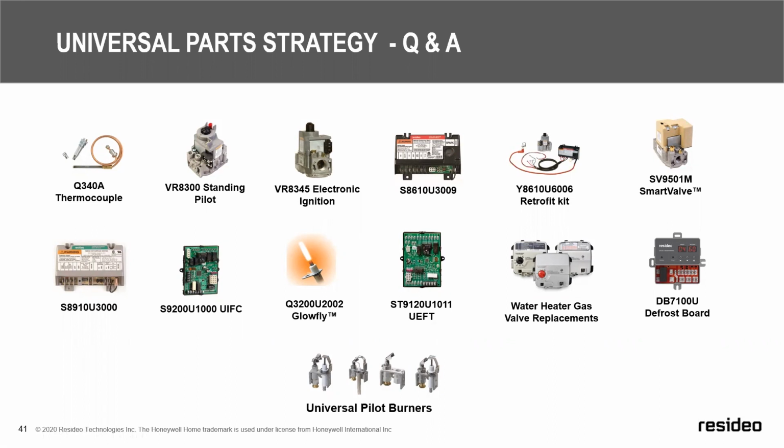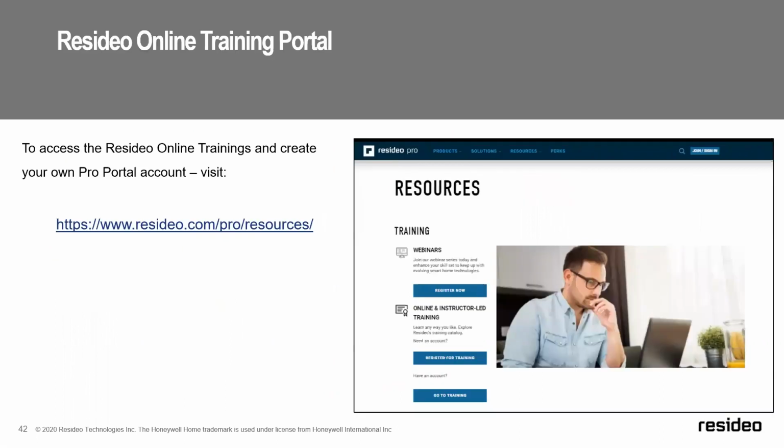Another one I have here is, on a gas valve, how do I select the best universal match? The answer to that is, what is the model number you're replacing? It's not that universal, as I say. They do replace a lot of them, but it depends on the opening characteristic of that valve. If you called me and I couldn't get the whole information on the gas valve, I really cannot cross-reference it, because I don't know how that valve opens. Is it a standard open, slow, fast, step? I have no clue. So I would sidestep and say, I just need more information.